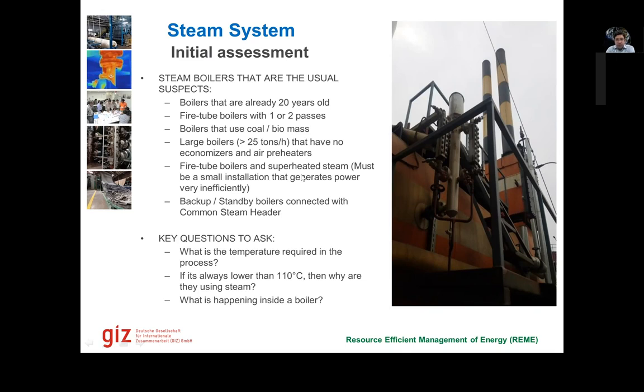Typical questions that we need to ask are, what are the temperatures that are required in the process? So if the process is requiring 60, 65, 70 degree temperature, why do we even make steam? Why don't we just heat up the water, use water heaters or solar water heaters, for example, instead of boilers, and directly feed hot water to the machines? That would reduce the heat exchange time and produce hot water. This is one question that we need to ask.